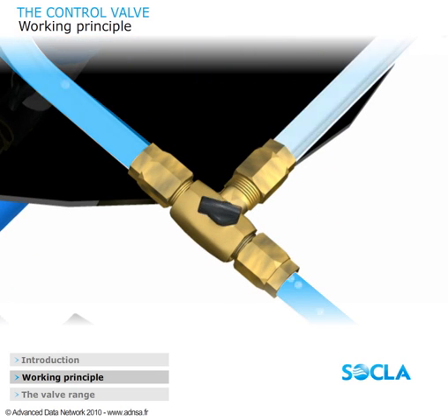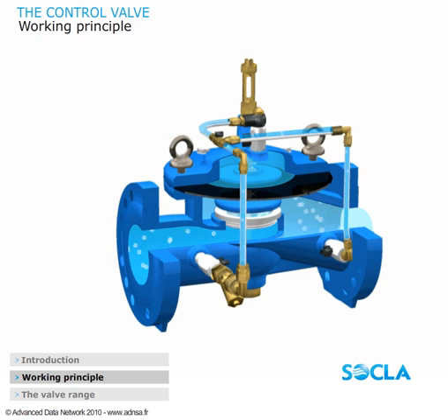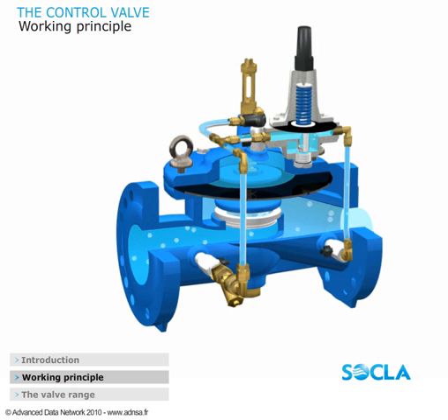Let's move the three-way valve. The three-way valve allows pressure from over the membrane to go downstream, thus freeing the closing system of the main valve, and it opens. In practice, this three-way manual valve is replaced by an automatic pilot valve which causes the movements of the main valve to follow it and thus ensure precisely all the different functions.